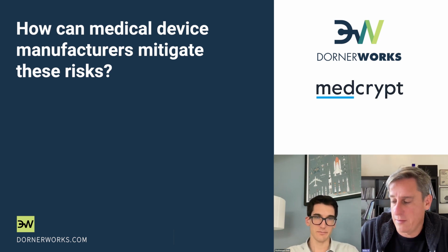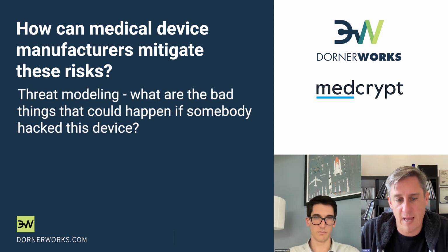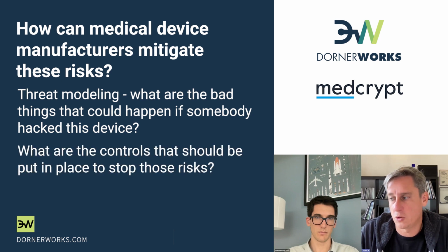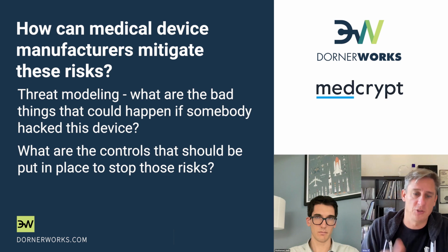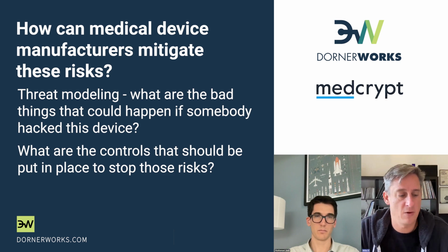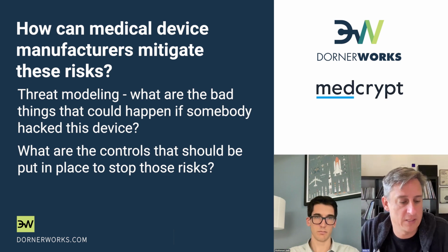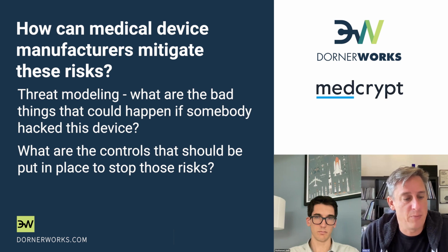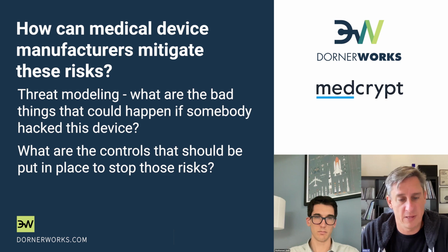Yeah, I think in the FDA guidance, they talk a lot about threat modeling. So essentially sitting down and saying, what are the bad things that could happen if somebody hacked this device? And once we identify what the bad things are that could happen, what controls should we put in place to stop those bad things from happening? And those are two very separate discussions, right? So I would recommend that if you're a device manufacturer building a device, be really thorough in asking that first question. What are all of the bad things that can happen?